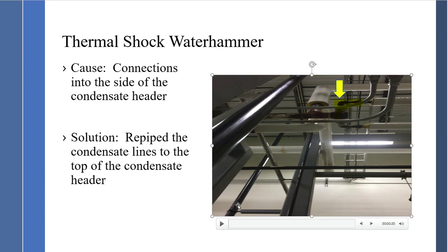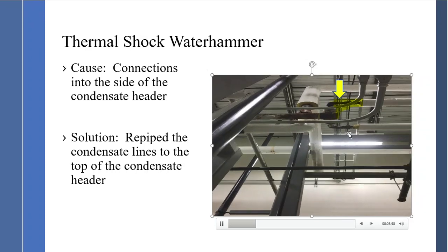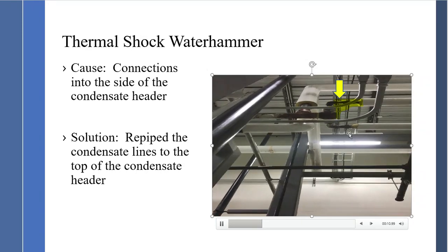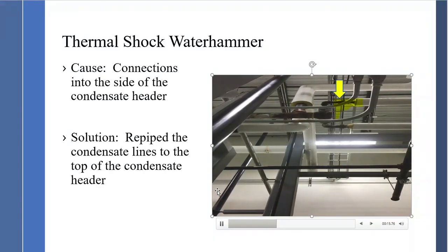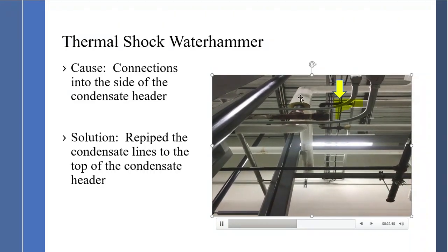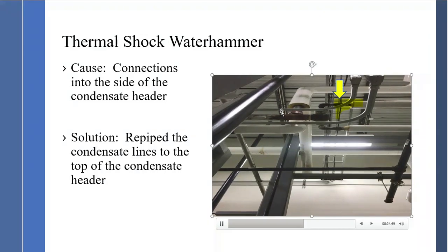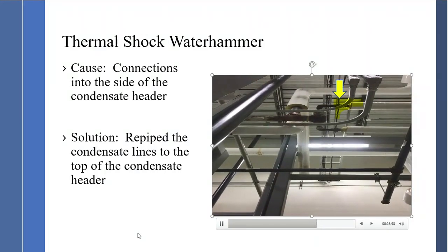Another application of thermal shock Waterhammer. As you can see, the connections up here go into the side, and you can hear the pinging noise and some of the movement occurring from the Waterhammer. So again, the solution: come back here and repipe, just like this condensate header here, to the top of the condensate header, and the Waterhammer will go away.